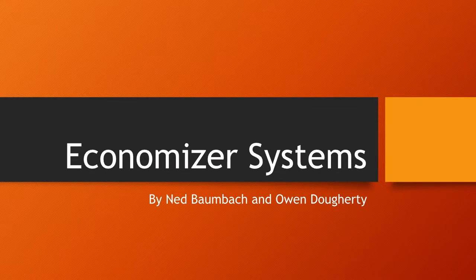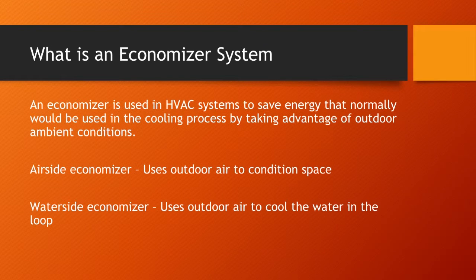So in every building automation system, in every building I should say, there's an HVAC system. HVAC systems by nature use a lot of energy to mechanically move heat from inside the building to outside the building. So sometimes the outdoor air is actually better than what we're trying to cool it down to. In that case, you use something called an economizer. So what is an economizer system?